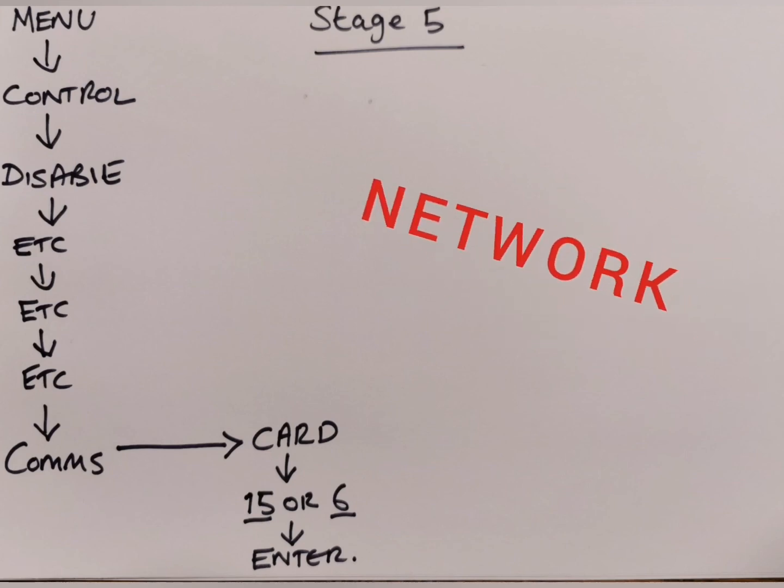To disable the network press the following: start with the menu button, then press the control button, then press disable. Now you have to press the etc button a total of 3 times. You may have noticed the button labeled comms situated above F1 but have been nervous about touching it. But fear not, press it, as this is the button you need to disable the Gent network.